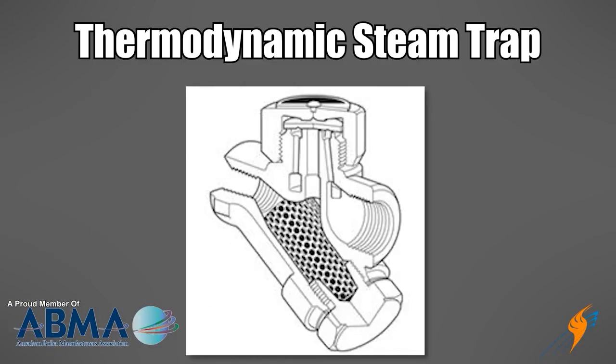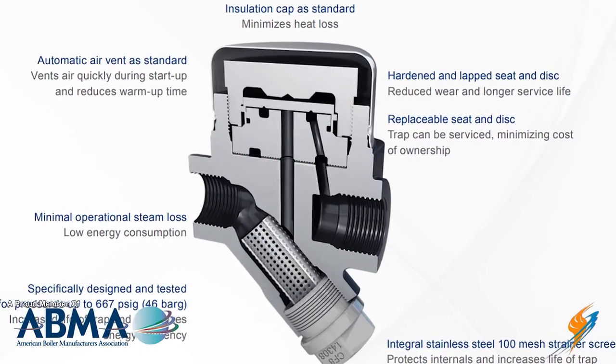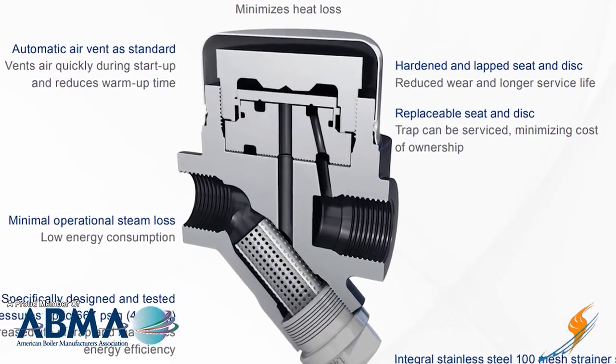So why don't we start with the thermodynamic and talk about what that actually is. It's a relatively small type of trap. It works on a mechanical feature where it utilizes high and low pressure zones, moving a disk up and down. Based on the velocities and the differential of pressures going through this trap, it'll either be stopping the condensate and the steam from flowing, or it'll be releasing it to come back and return.